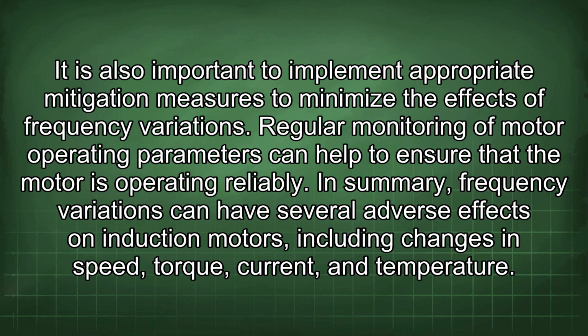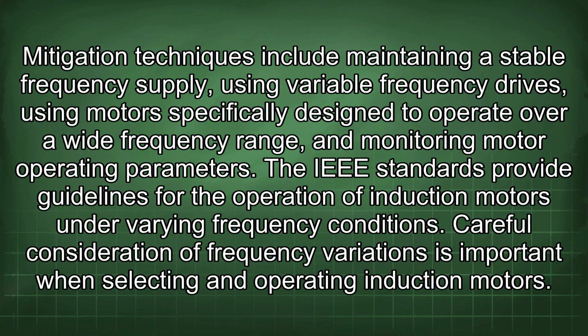In summary, frequency variations can have several adverse effects on induction motors, including changes in speed, torque, current, and temperature. Mitigation techniques include maintaining a stable frequency supply, using variable frequency drives, using motors specifically designed to operate over a wide frequency range, and monitoring motor operating parameters. The IEEE standards provide guidelines for the operation of induction motors under varying frequency conditions. Careful consideration of frequency variations is important when selecting and operating induction motors.